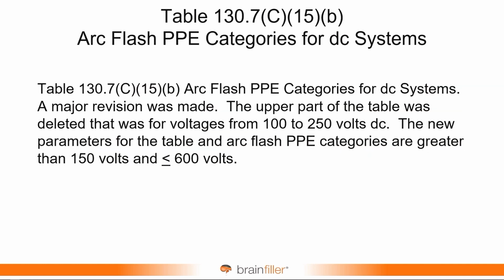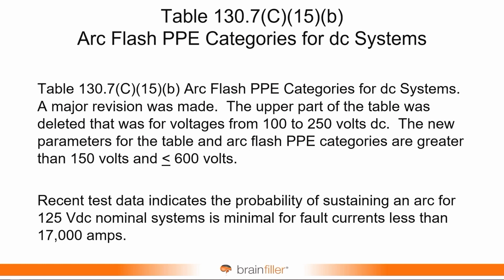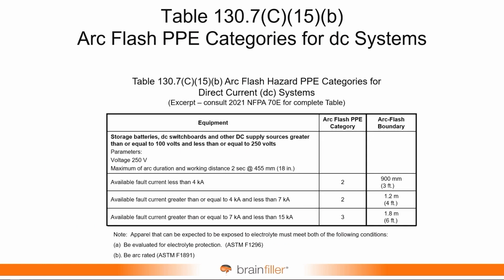PPE categories for DC systems. DC continues to evolve. And with DC, when it comes to arc flash, there is a table in NFPA 70E. In 2021, there were actually two tables. There was a table from 100 volts to 250 volts, and then another from 250 up to 600. Well, the table from 100 to 250 was removed because recent test data shows the probability of sustaining an arc for 125 volts DC is minimal for fault currents less than 17,000 amps. Now, I have to clarify, this is not based on IEEE 1584 data. This came from another source. But because of this data, stating the probability is pretty remote for sustaining an arc flash, we now just have one table.